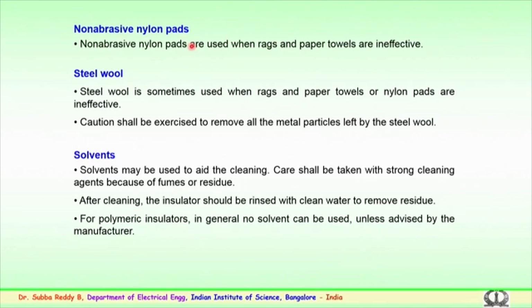In case of polymer strings or insulators, in general no solvent can be used. This is an important point to be considered, particularly unless it is advised by the manufacturer. Polymer insulators, again I am stressing here, are organic in nature. The rubber surface of the sheds, in case of using solvents, chemically reacts, and this could degrade the hydrophobicity characteristics of the rubber surface.